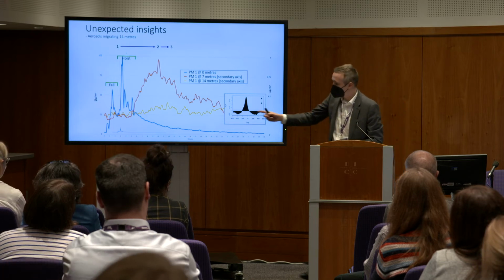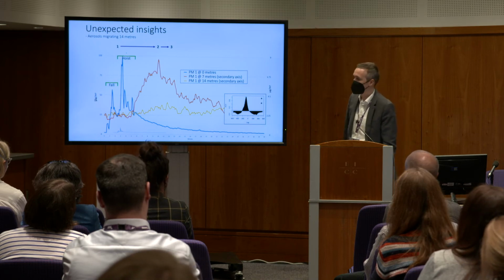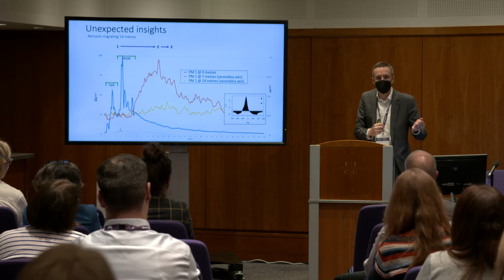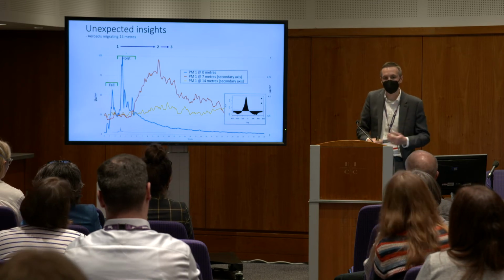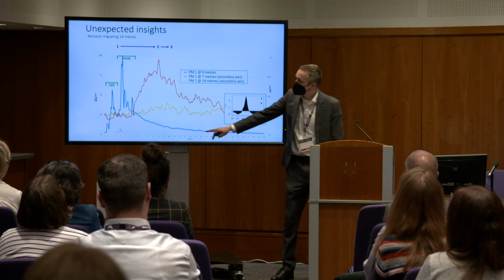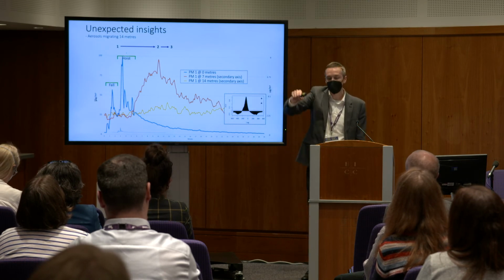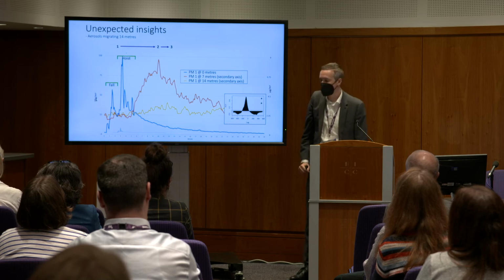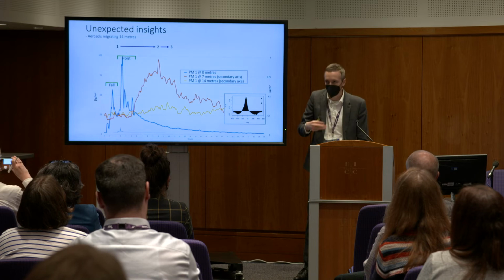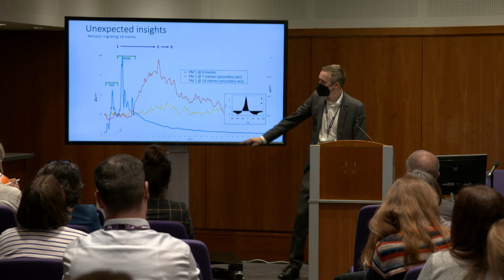Interestingly, that's the first bit, the first spike. And then what happened is lots of staff eventually realised that someone's on the floor and rush in. So 4 staff had to get a big piece of equipment, a full hoist, and hoist her back into bed. Luckily, no injury. But that spike in particulates at sensor 1, which was directly opposite her bay, is getting the full force of those environmental aerosols. These are not necessarily infectious aerosols, but they're dust, lint from clothes and things. They're in the sub-micron range, so they're the small floaty ones.